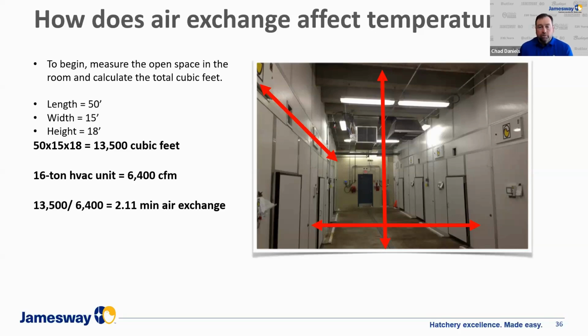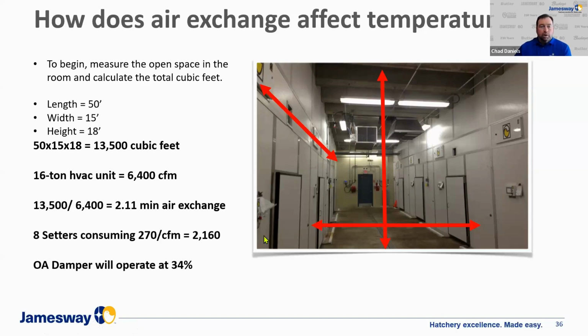It's because we've confined the space too much, and the rooftop unit isn't designed to fit this particular type of application. In some cases, hatcheries want to build a drop ceiling across here. Well, this 2-minute air exchange may end up as a 1 minute and 20-second air exchange, so your problem just gets worse. We do the quick math on this, and it tells us our outside air damper is going to function around 34% when we're feeding the 270 CFM per incubator.